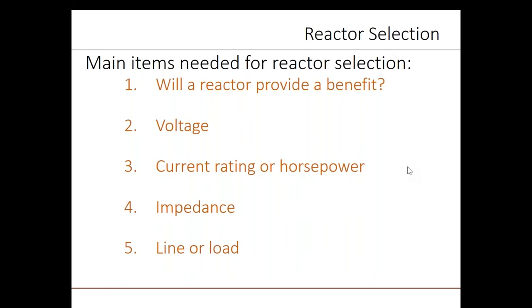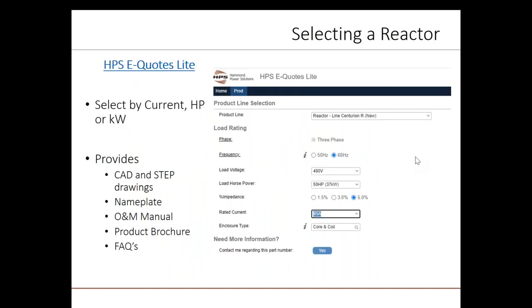We've been through all the benefits of line and load reactors, and all the considerations to do with voltage, current, impedance, and line or load side. Now let's look at how we can put all this together and apply this knowledge in selecting a reactor. eQuotes Lite is an online configuration tool on the HPS website at americas.hammondpowersolutions.com. By clicking the drop-down menu for resources towards the right side of the page, you can find the product configurator. Then you simply fill in the frequency, voltage, horsepower, kilowatts, or current, and select the impedance. The system will then size the best reactor for your application.